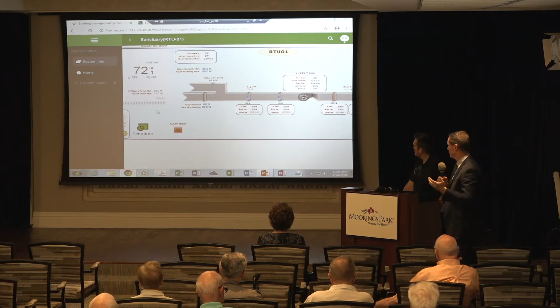Bauer Chapel's set up that way, correct? Yes, sir. Bauer, we set up with occupancy sensors. There are sensors in Bauer Chapel that detect occupancy via CO2 emissions from all the occupants, and that will change our set point. So when it detects people in Bauer, it will call for cooling and also open the outdoor air dampers and bring in more fresh air. And this can all be set up through our building management system.